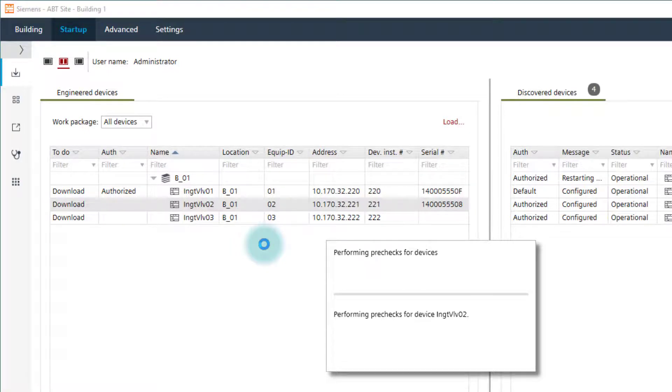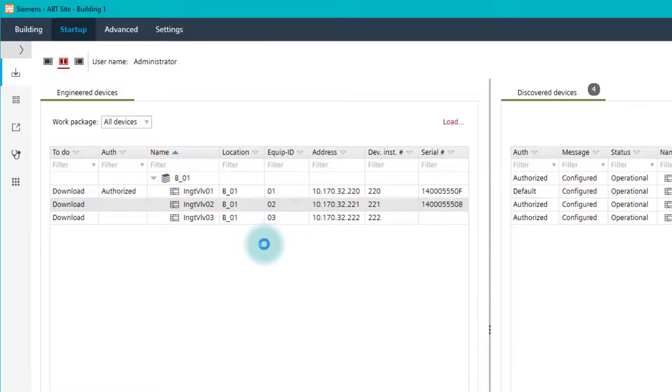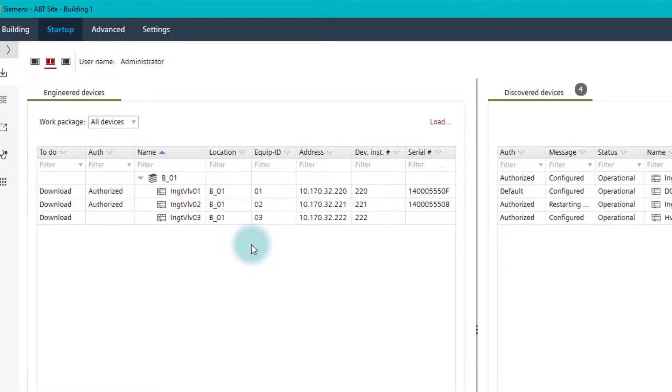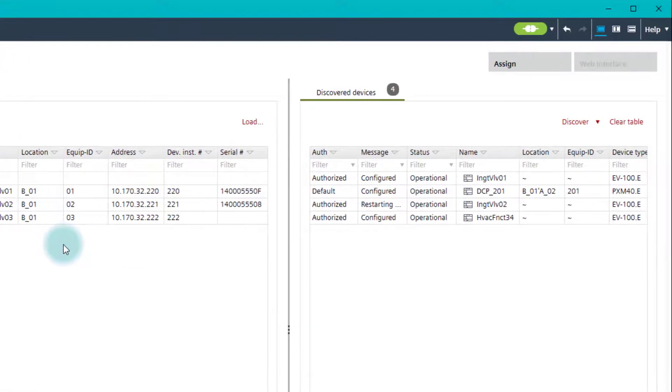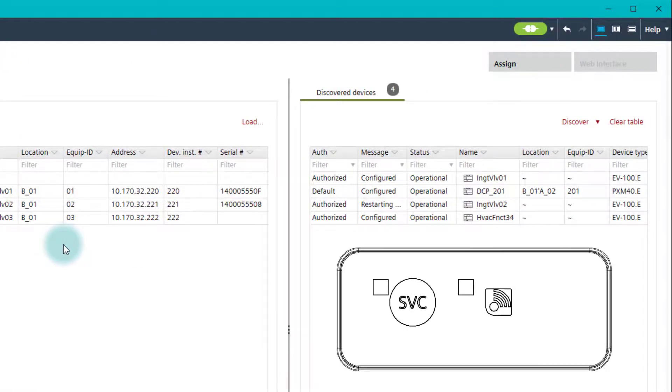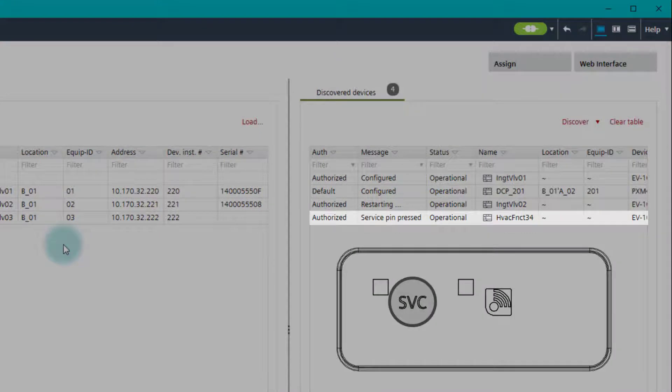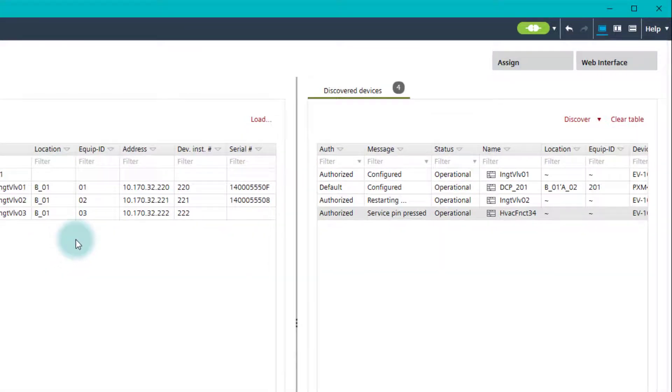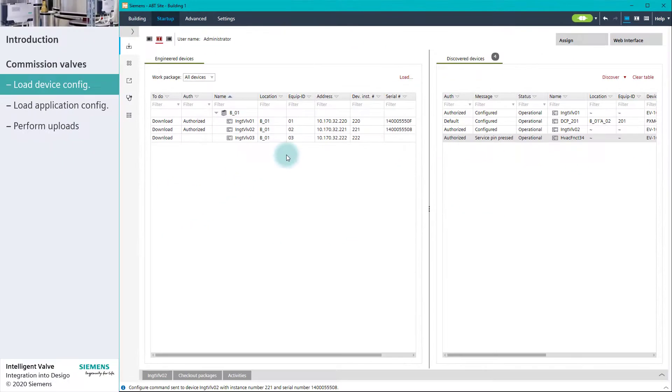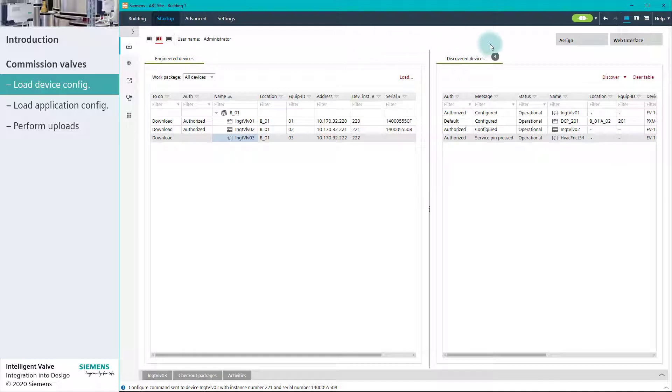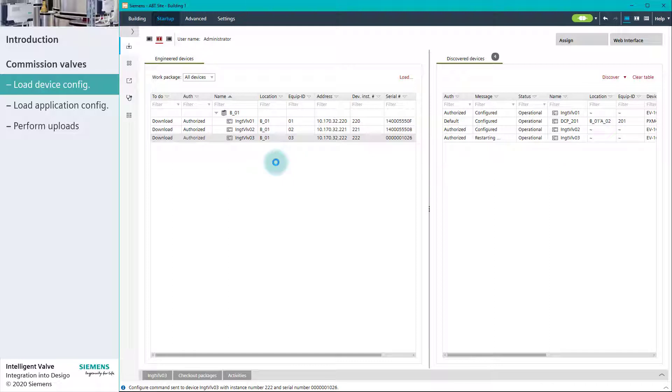Now, what can we do if the serial number of the intelligent valve was not written down during installation? No problem. We have a solution for that too. We walk to the physical location of the device and press the service button. ABT Site shows us the device with the active service pin. We simply assign this device to the intelligent valve with the missing serial number. This completes the download of the device network configurations.